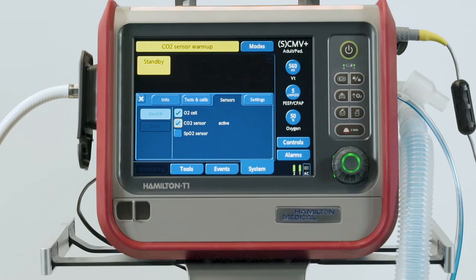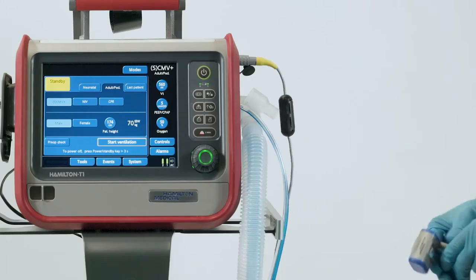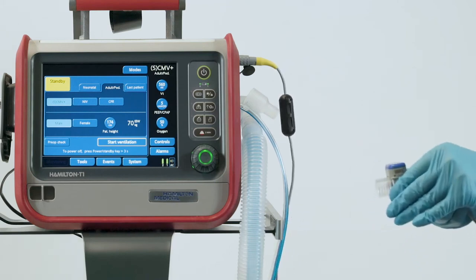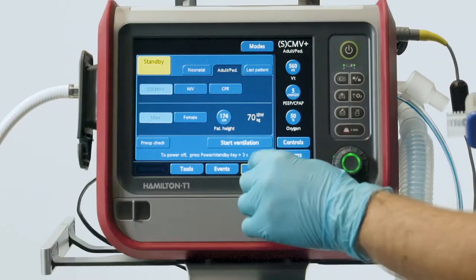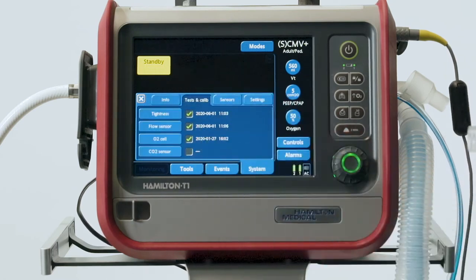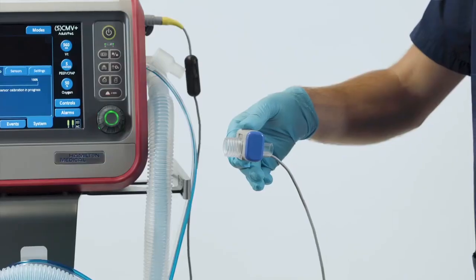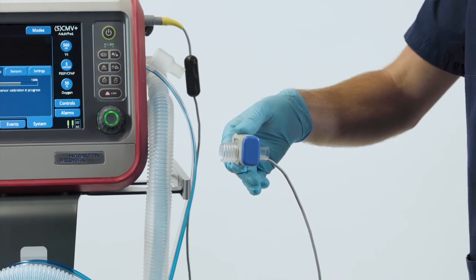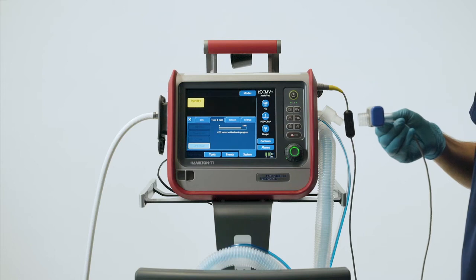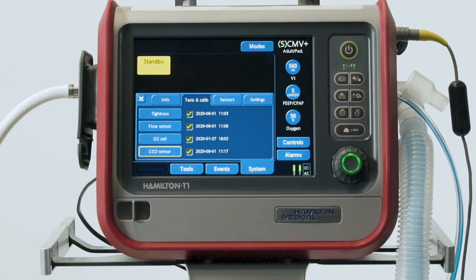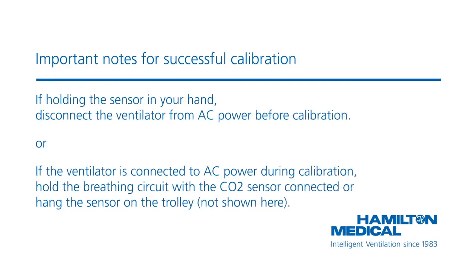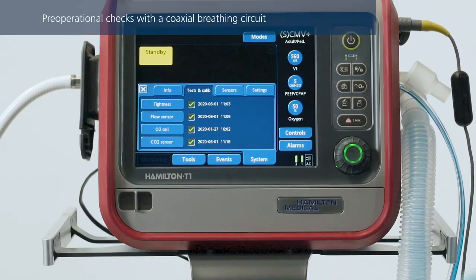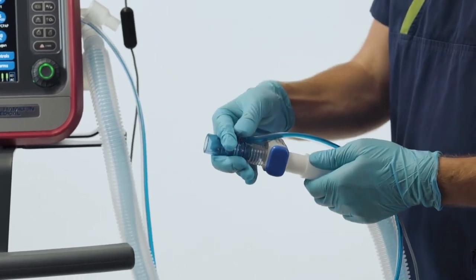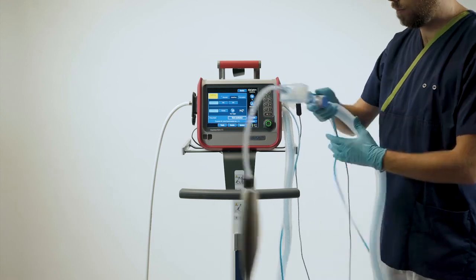If you haven't already connected the airway adapter to the CO2 sensor, do that now and make sure you keep these components away from all sources of CO2 and the exhaust port of the expiratory valve. It is important not to move the CO2 sensor during zero calibration. When zero calibration is complete, you should see a green check mark in the CO2 sensor checkbox. If you're using a coaxial breathing circuit, do these pre-operational checks before you connect an HME filter. Once you've done the test and calibration, you can place the HME filter between the patient and the flow sensor.